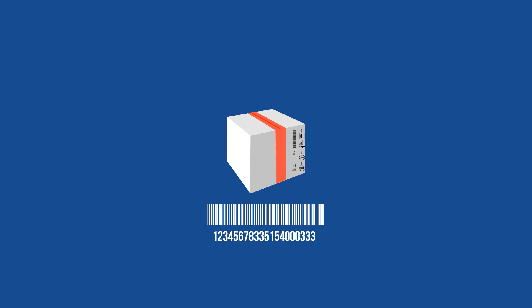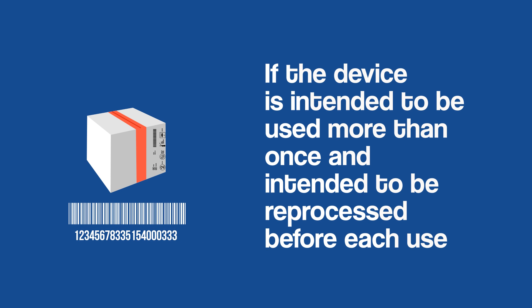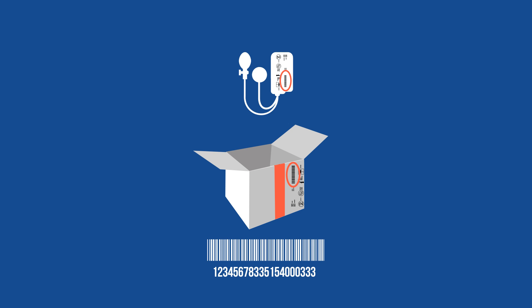UDIs must be included on device labeling and must be displayed in human-readable and machine-readable format. If the device is intended to be used more than once and intended to be reprocessed before each use, the UDI must also be placed on the device itself.